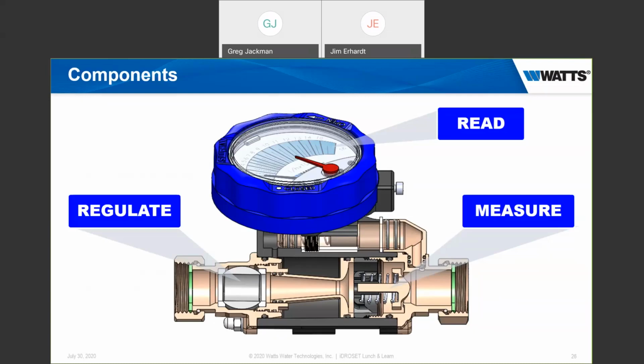For the more technical people who are familiar with balancing valves, you're going to notice a Venturi in there. You're also going to notice a check valve, and this is a patented design that uses a Venturi and then uses this check valve, which is not a conventional check valve. It's not going to prevent backwards flow, but rather it's a valve that helps improve the accuracy at the low range of the reading.